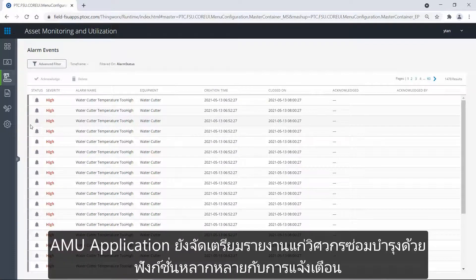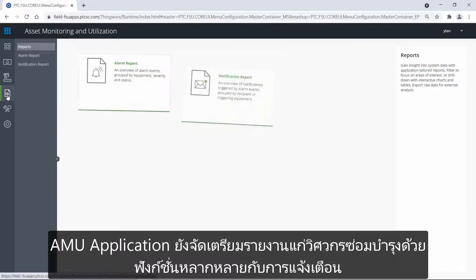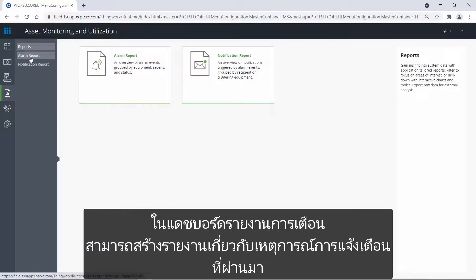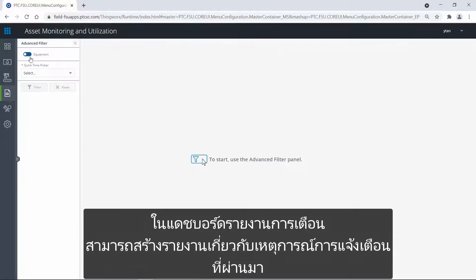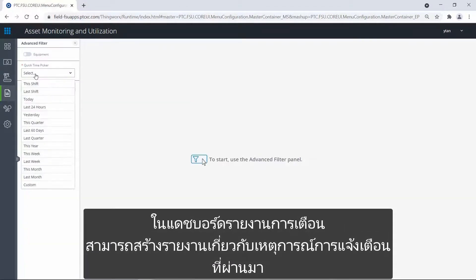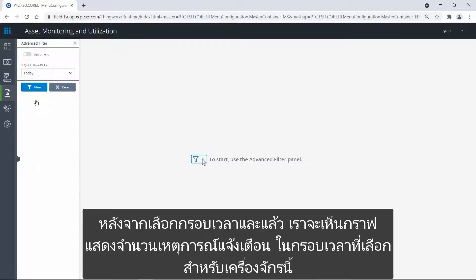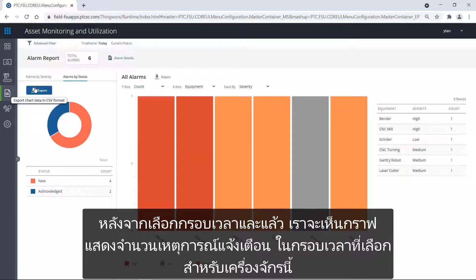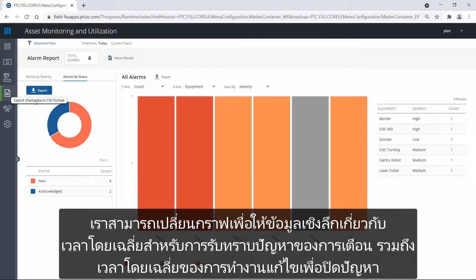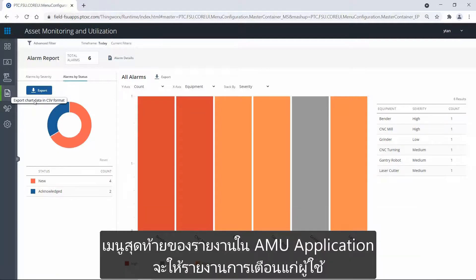AMU also provides the maintenance engineer with reporting functionality around alarms. In the alarm report dashboard, I can generate reports around past alarm events. After selecting a timeframe and equipment, we see a graph showing the number of alarm events in the selected timeframe for this asset. We can change the graph to give insights into the average acknowledgement time of alarms in hours, as well as the average closing time.